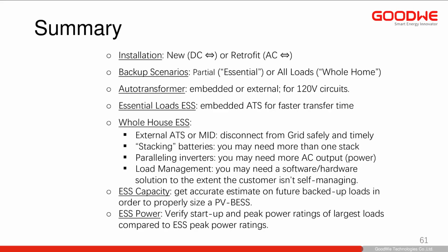In summary, we can do retrofits and new installs, partial and whole home. Make sure you have an auto transformer, either embedded or external, since you'll want to power 120 volt circuits. Also know that an auto transformer can handle imbalanced 120 volt loads. If you have two 120 volt bus bars in that essential loads panel, do they need to be within 30% of each other in usage? Some systems don't require that balancing—GoodWe doesn't.